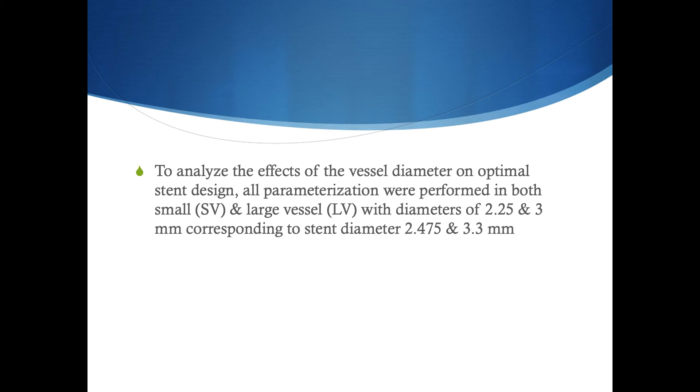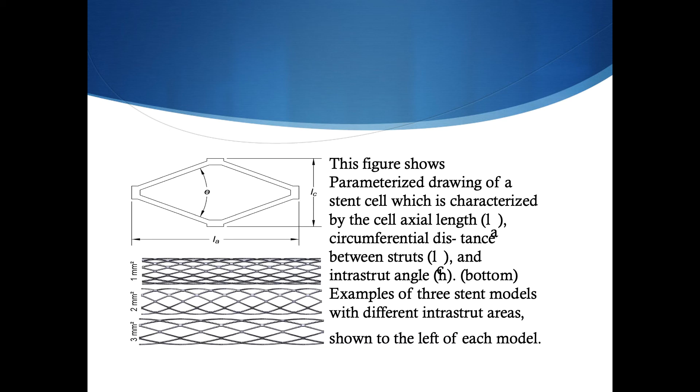After analyzing the diameter and length of the vessel and the designated optimal stent design, we achieve the optimum length of 2.25 and 3 millimeters to diameter of 2.475 and 3.3 millimeters.